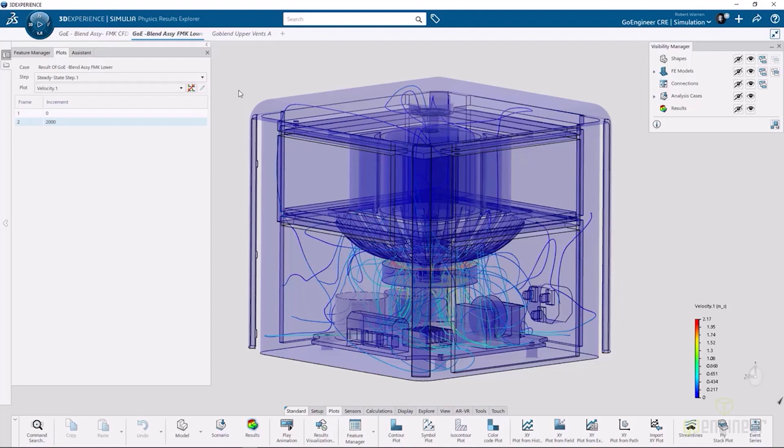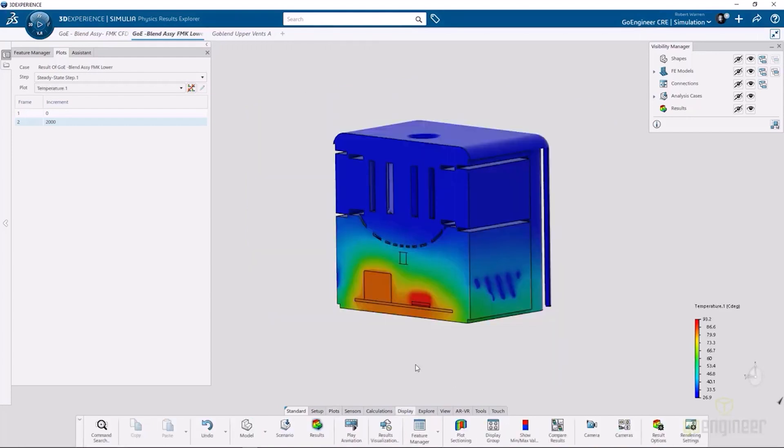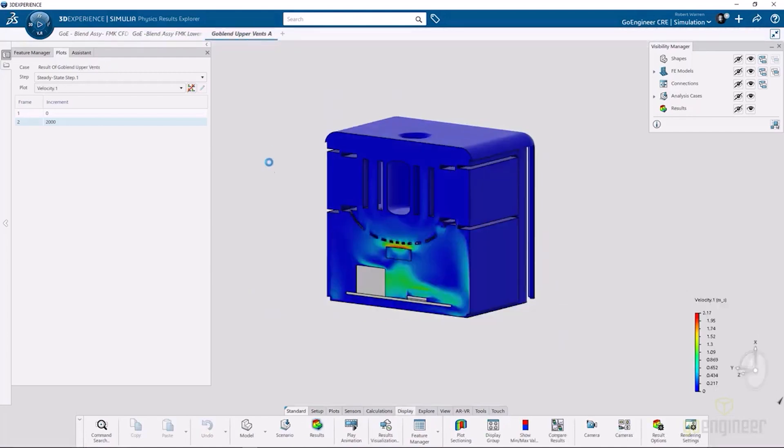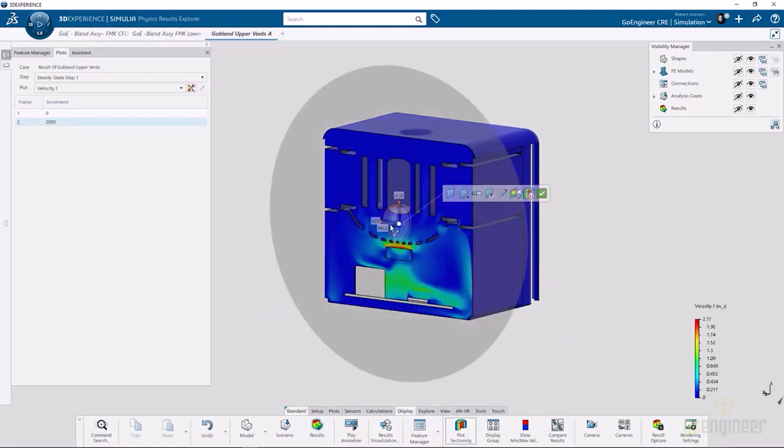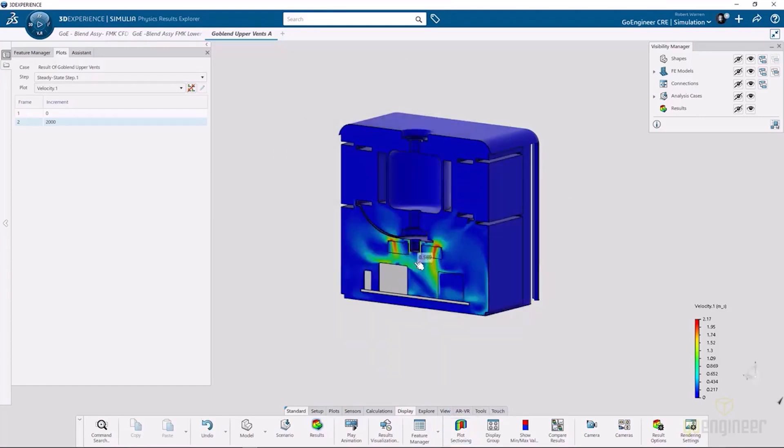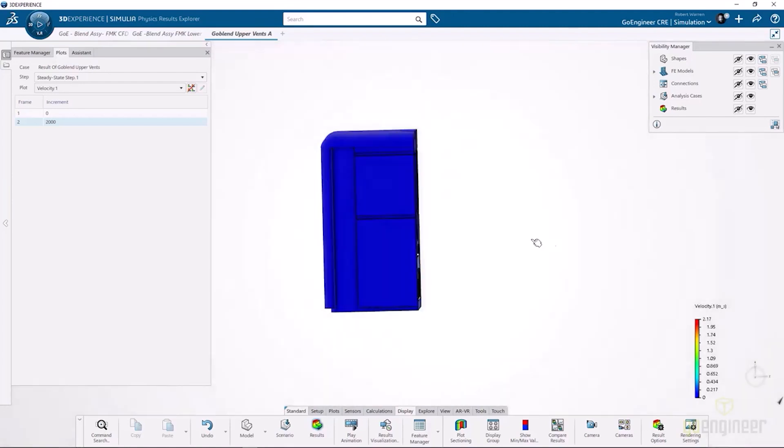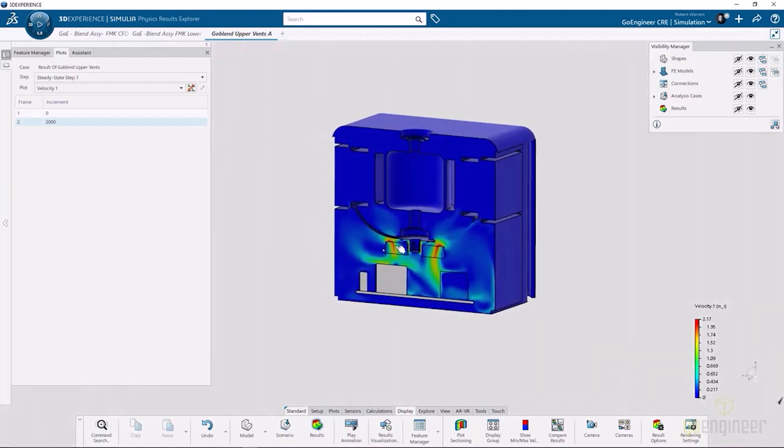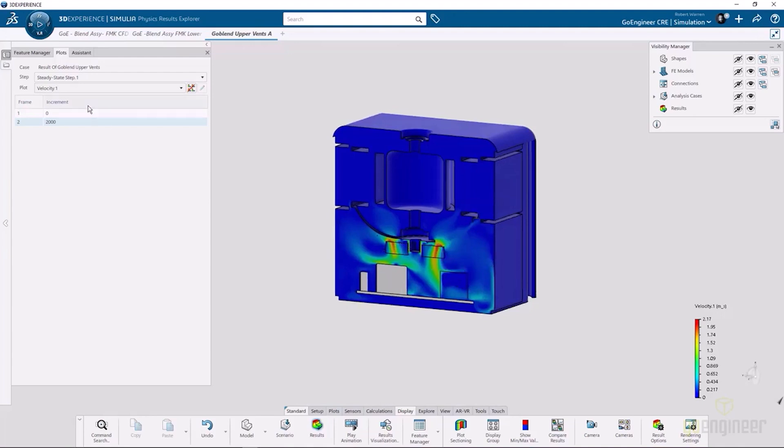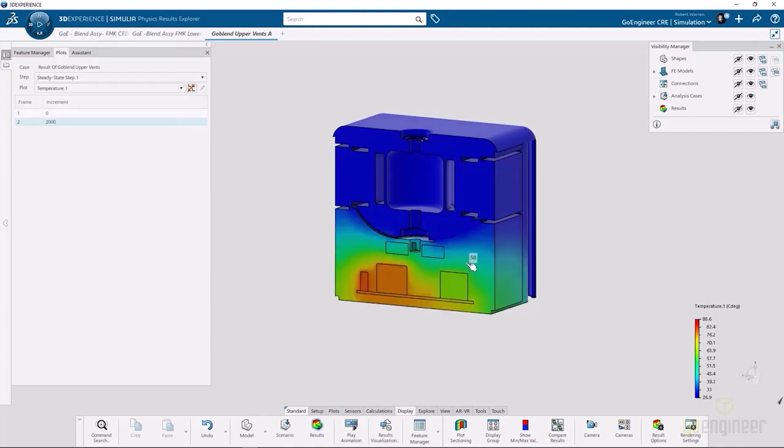Now let's look at the upper vents. This is the upper vents only. Again, we're looking at velocity. We can do a plot section on this, kind of get a feel for what that velocity looks like. In through the fan we're kind of dead ending the fluid. You can see a high velocity up against the wall and it's kind of recirculating, but we're not getting any movement there. Not quite what we wanted.